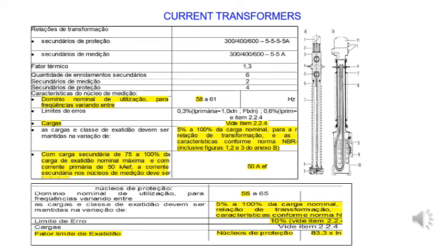And in the case of the measuring cores, we have some tests also to assure that if a short circuit occurs and passes through the primary winding, the currents, and this is the contrary of the protection cores, are limited to a value of something like 50 amps, because it's not the function of the measuring core to reproduce the currents for very high values of short circuits.